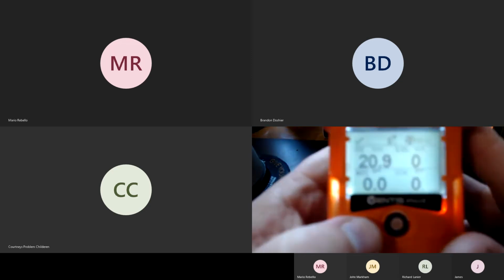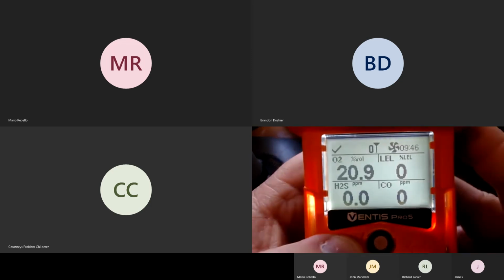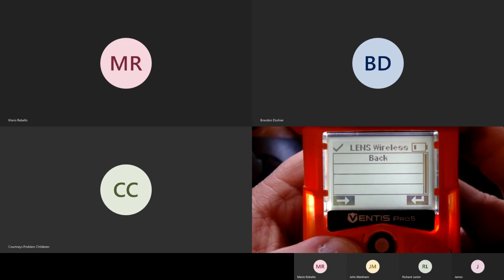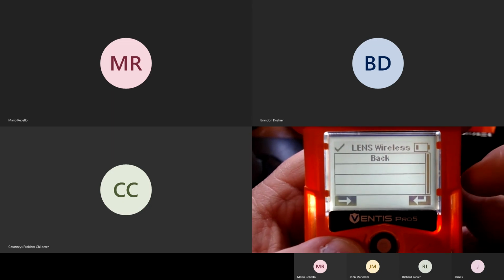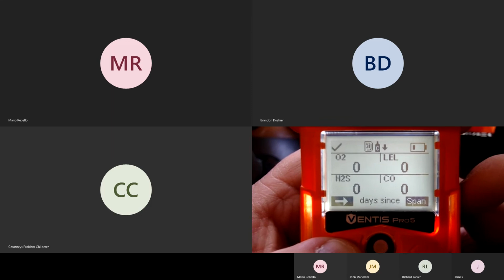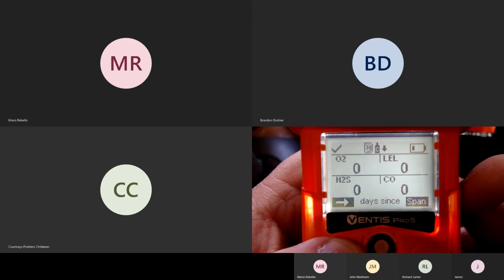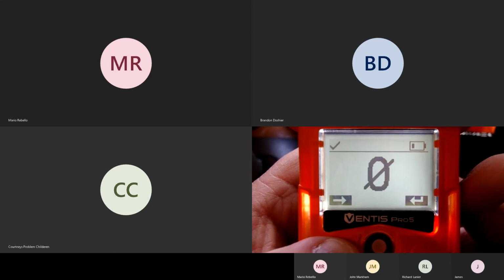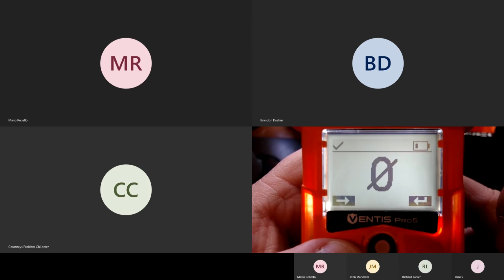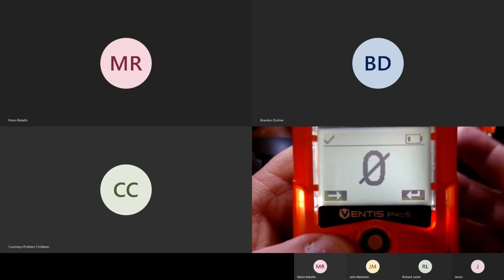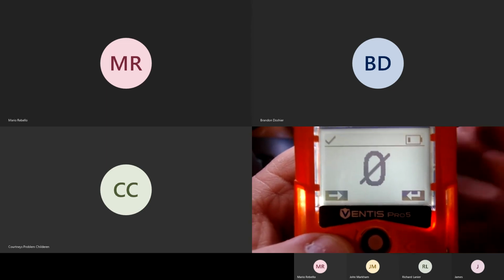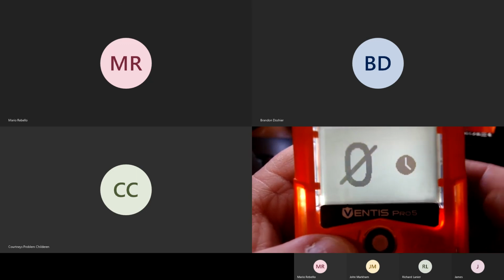All right, so to navigate through, I'm going to click the power button, which is my left-hand power button. And first screen is my lens wireless. Next screen is how many days since calibration. And then the next screen is my zeroing function, the big 0 with the line through it. This is what I was talking about. So after you turn the instrument on, you're going to want to come here. You hit the enter button, and that starts the zeroing process.